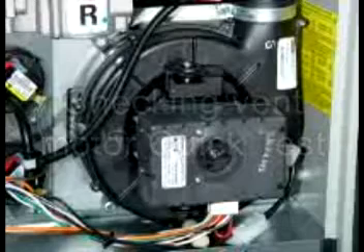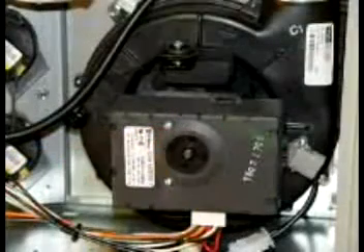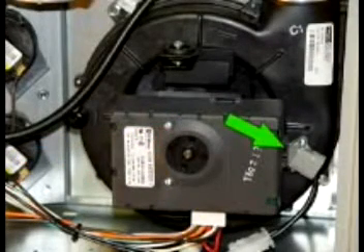Checking vent motor quick test. If the induced draft blower does not run, make sure there is 115 volts to the vent motor 12-pin plug. Check the voltage between neutral and pin 12 of the 12-pin plug on the vent motor. If voltage is not present, check to make sure the induced draft blower limit is closed. If it is open, replace it.